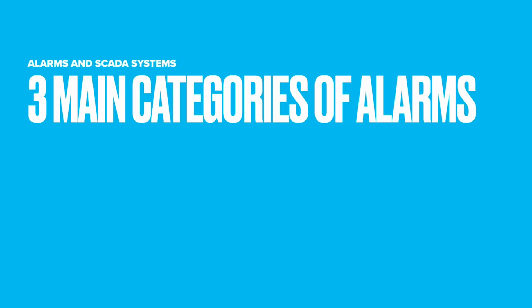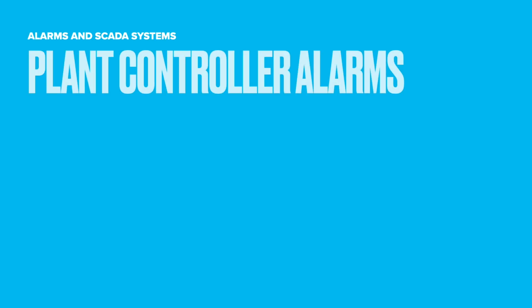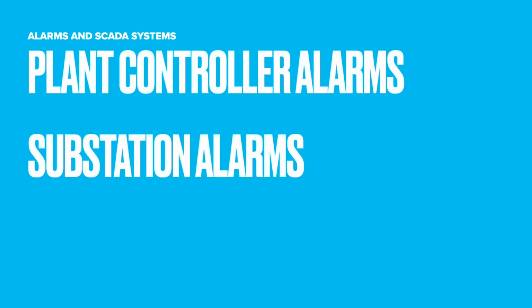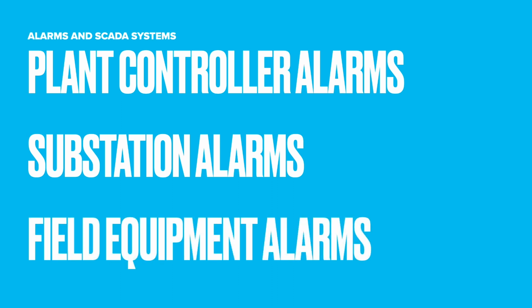There are three main categories of alarms: plant controller alarms, which would include site control mode statuses and interconnect compliance issues; substation alarms to indicate the health and statuses of the substation protection, switching, and transformer equipment; and field equipment alarms from inverters, trackers, and MET stations.